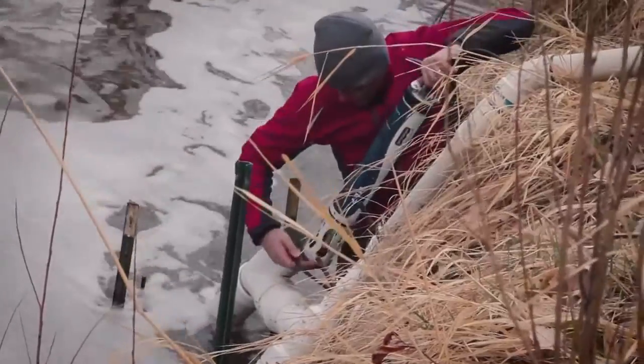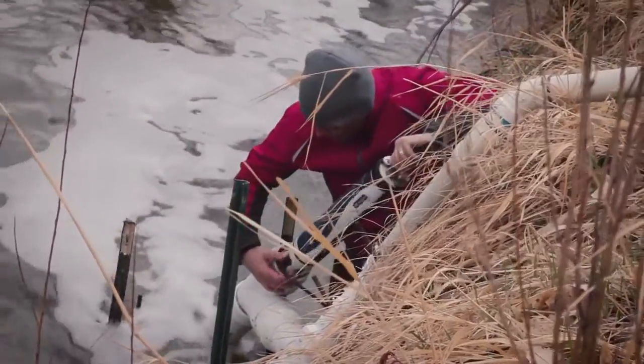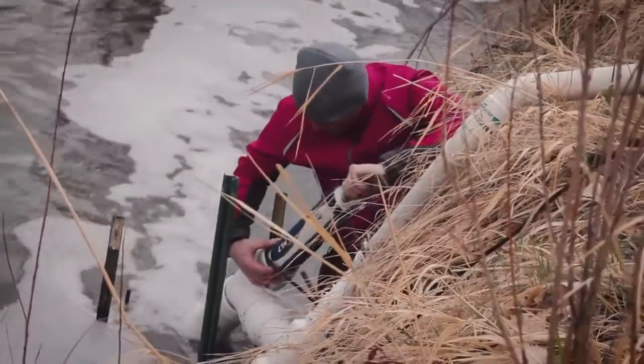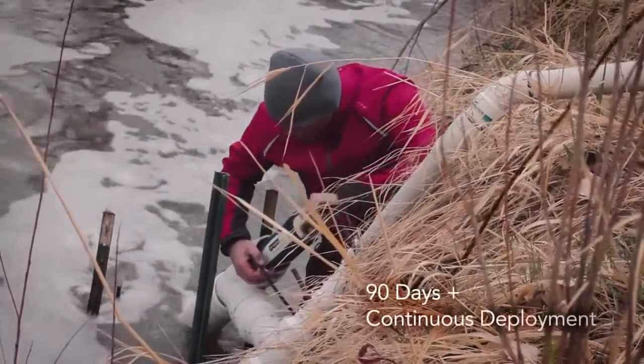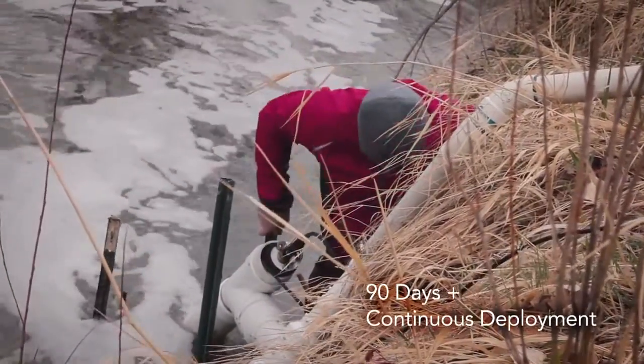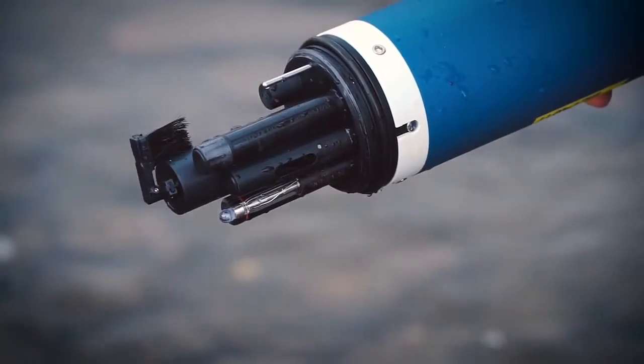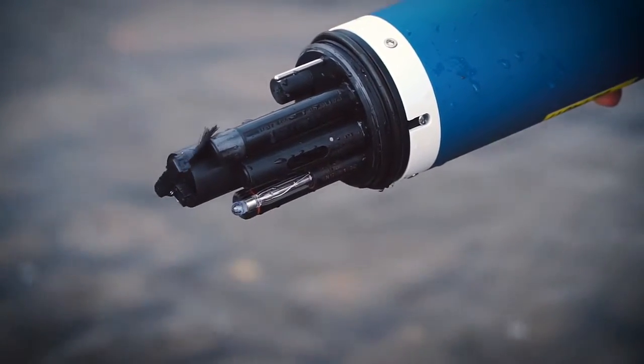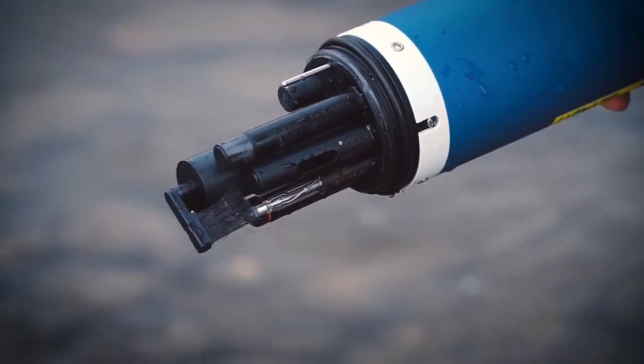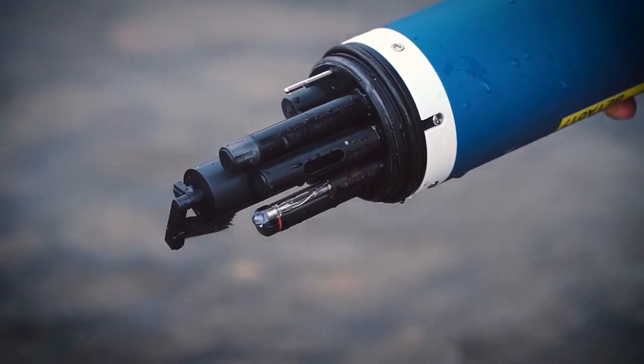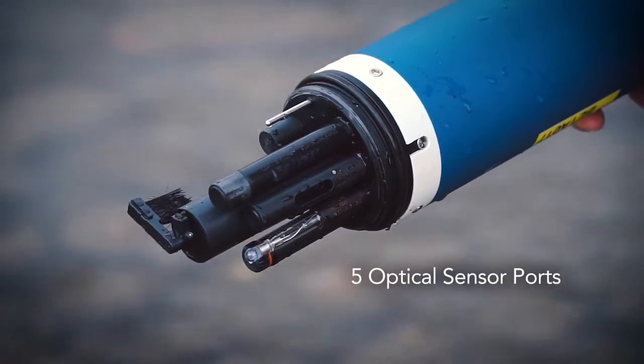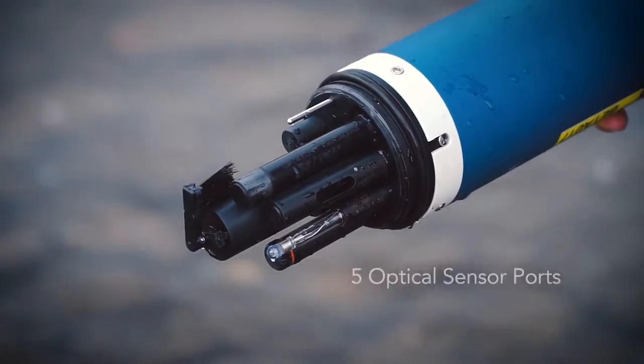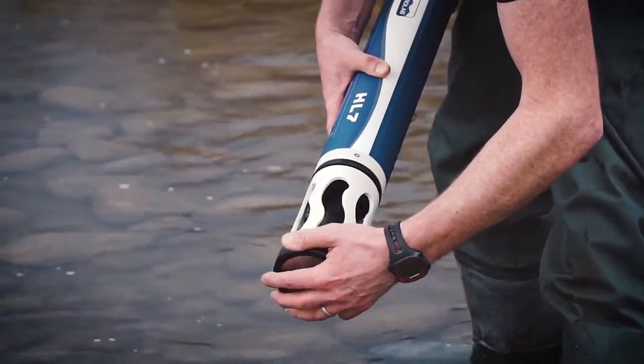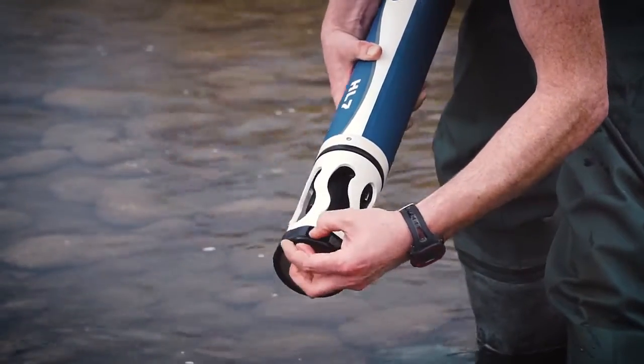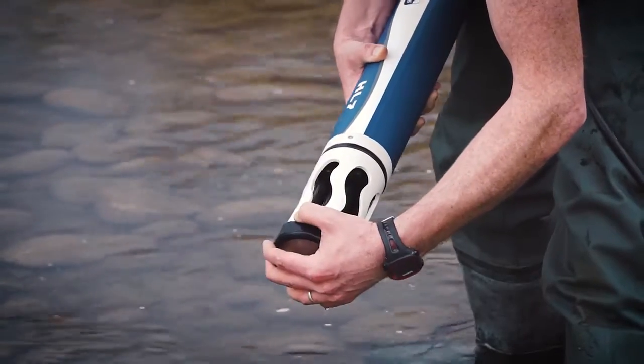Designed and tested to withstand the heavy everyday use of demanding field deployments for continuous monitoring, capable of greater than 90 days deployment. Significantly extend field use with proven sensor technology combined with a central anti-fouling cleaning brush. 5 optical sensor ports expand the number of parameters. Durable sensors help maintain a cost-effective water quality monitor.